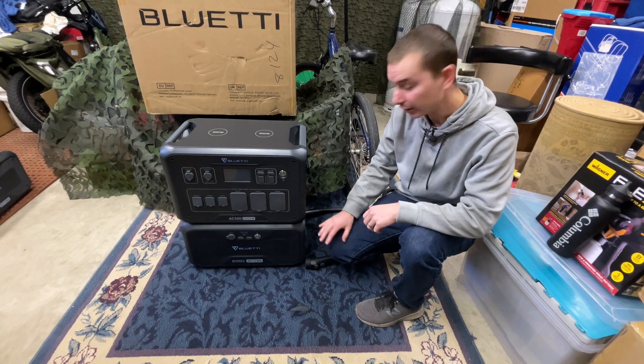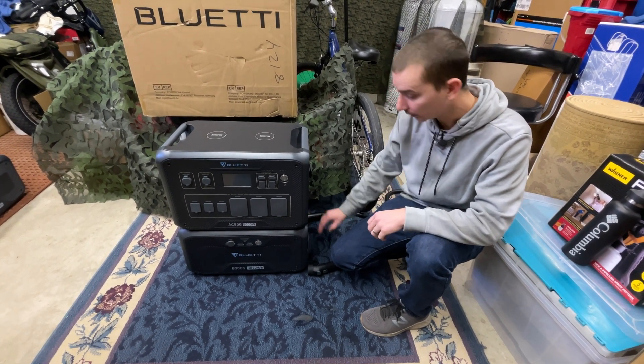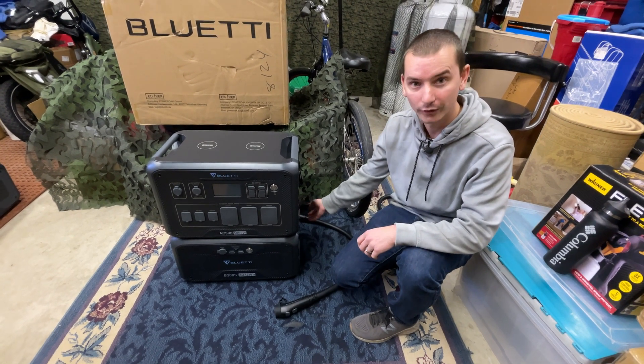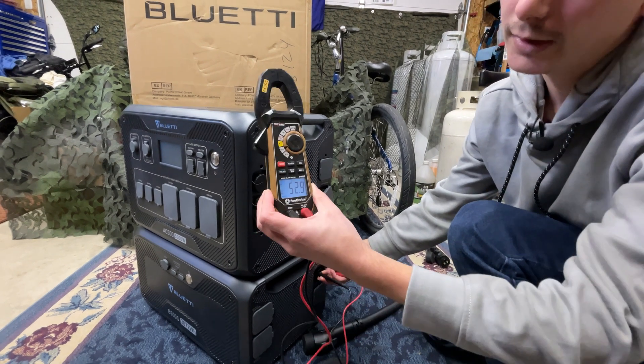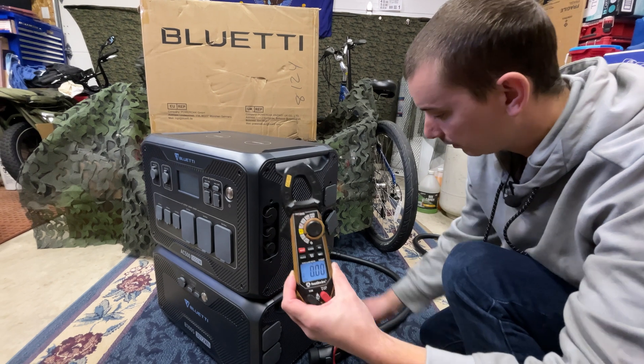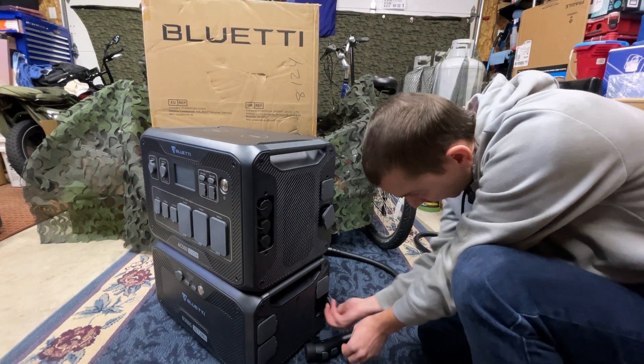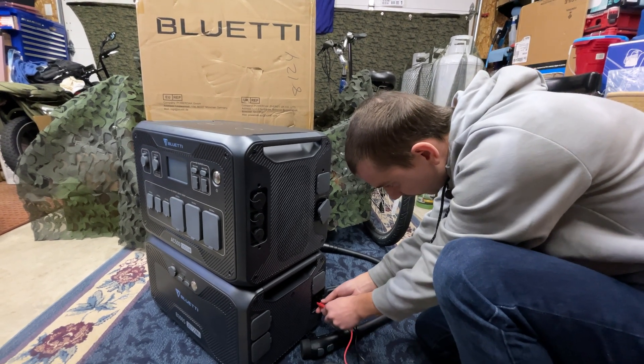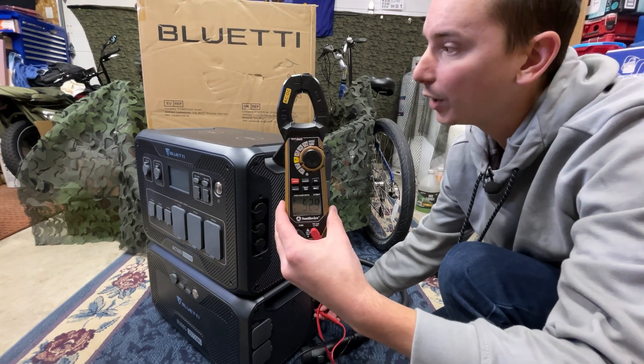So now we just have the bad one here, and just for fun I'm going to take a multimeter to the output port on this as it sits without plugging the cable in, to see if we have any output voltage right now. Our battery one port says 52.9 volts. Checking the bottom one — yeah, also 52.9.